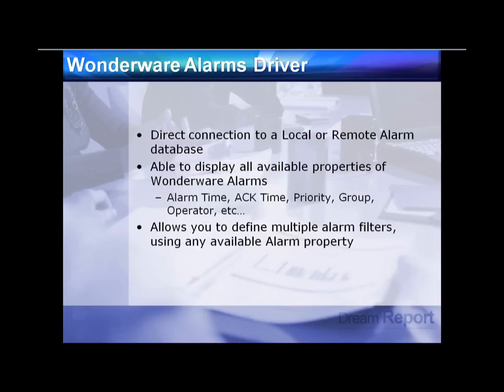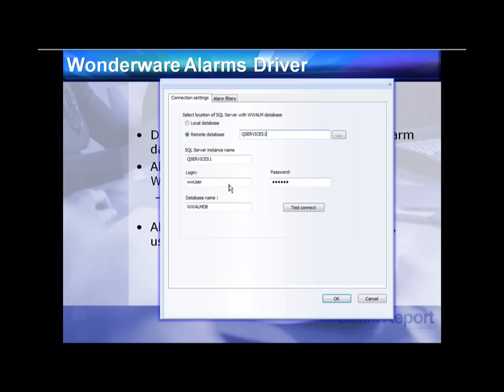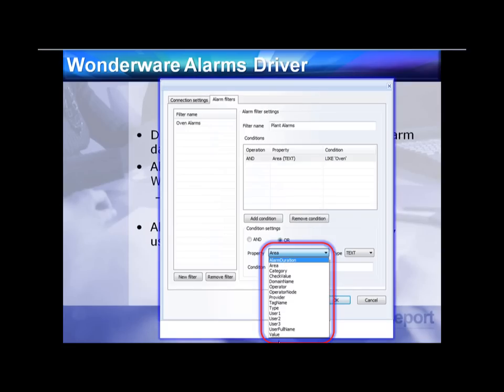The Wonderware alarms driver provides direct connection into any local or remote alarm database, displaying all available properties of alarms and events. You can pre-configure multiple alarm filters — for example, high-priority reactor alarms — by filtering by alarm group, duration, area, or operator, then creating a logical expression such as alarm group containing 'ovens.' These filters are then selectable when configuring a report.